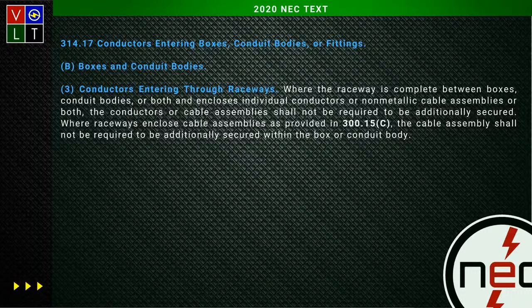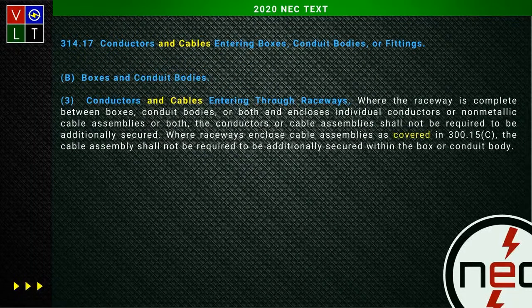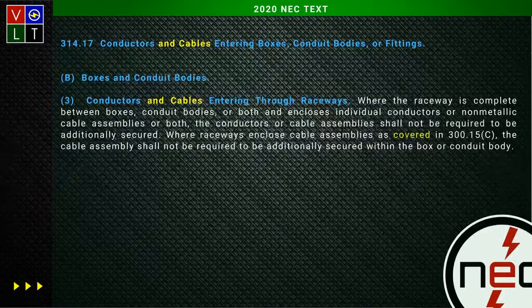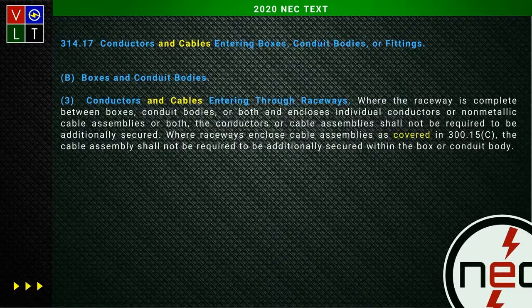One of the proposed changes we'll get to later, when you come over here, you'll notice in the heading they put 'and cables.' They wanted to be very specific about non-metallic sheathed cables, and this is just covering that. Then it refers you to where it's covered in 300.15C about not being required to be additionally secured within the box or conduit body.